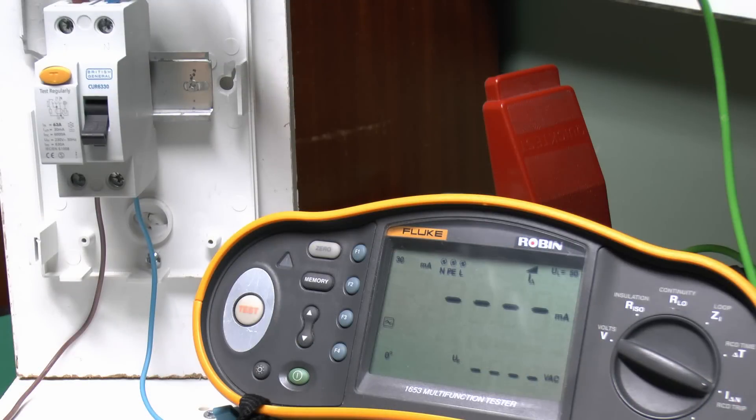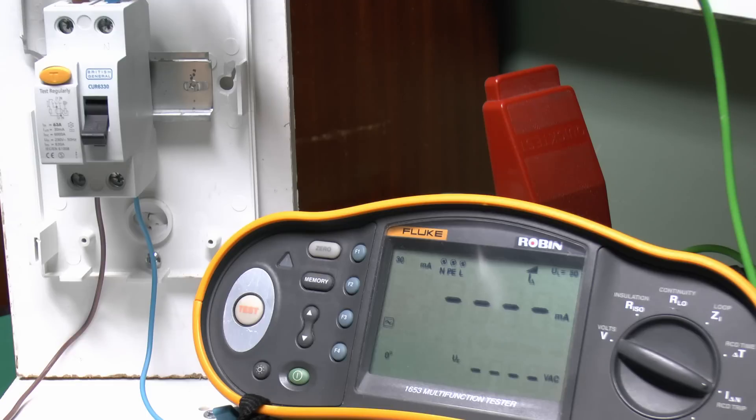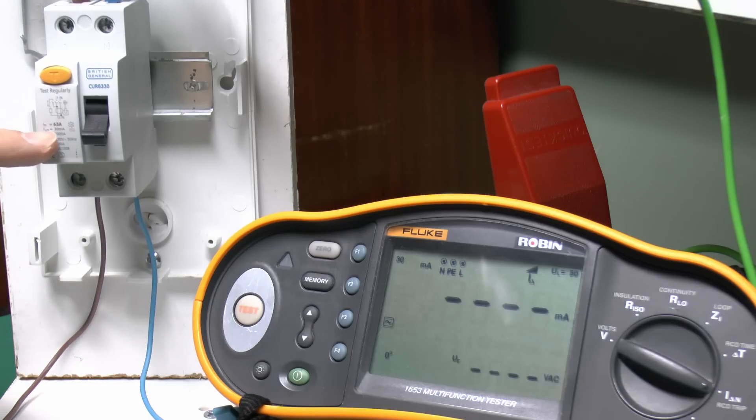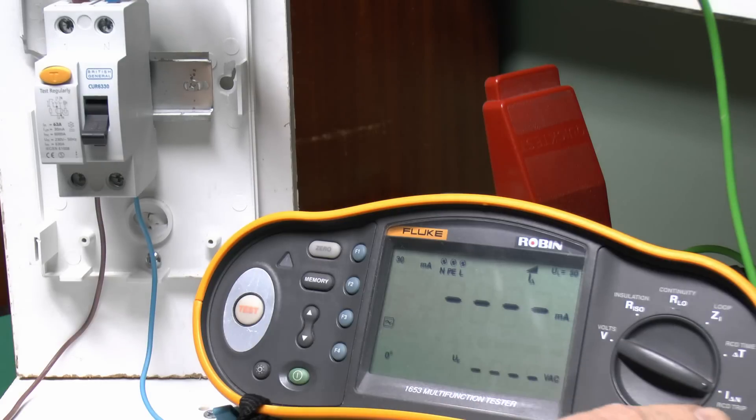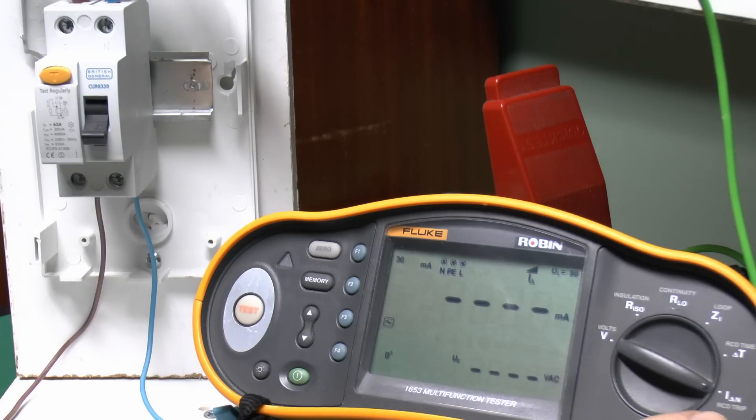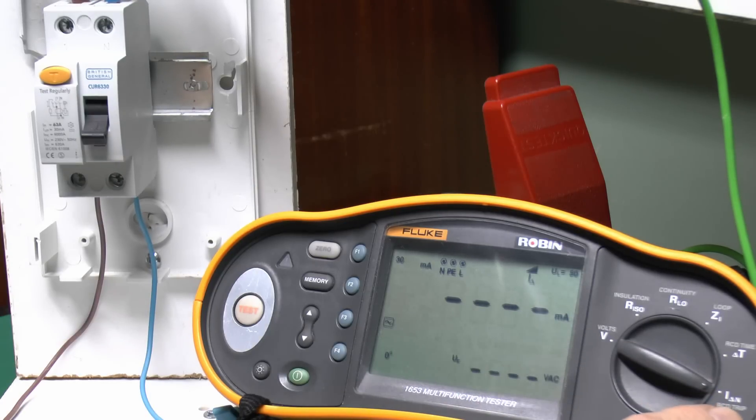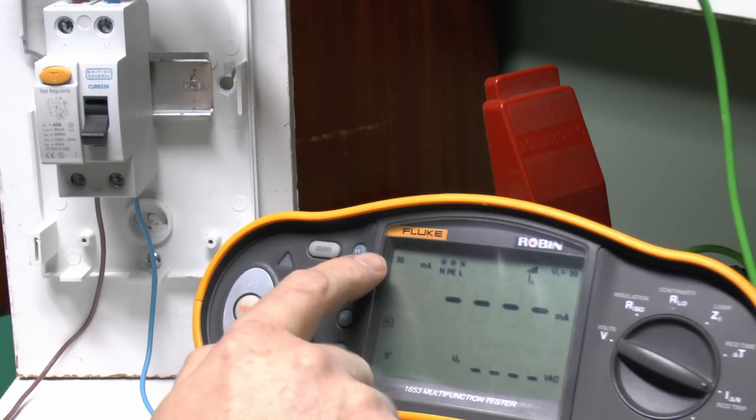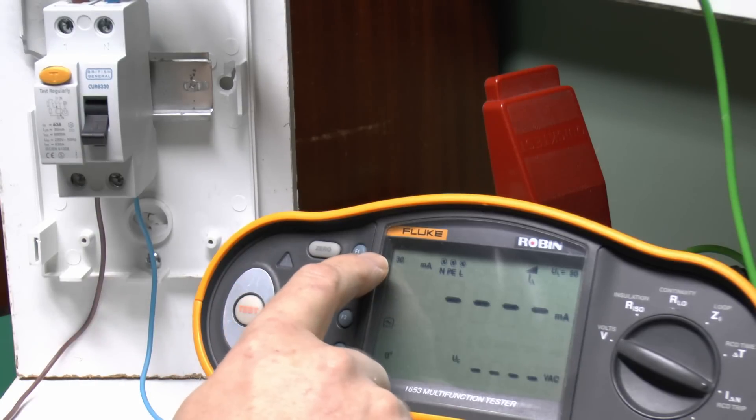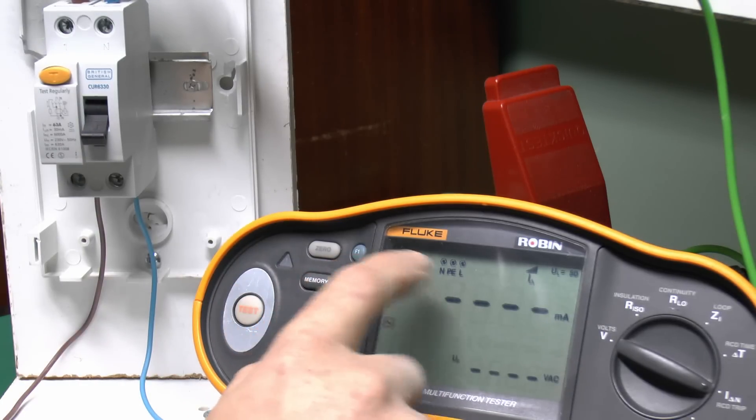Now, there's two basic types of tests which you can do on RCDs and the first one is the current it actually needs to cause the device to trip. And in the case of this particular one, it's a 30 milliamp device, so you would expect it to trip at or slightly below that tripping current. And to do this, we'll just select the appropriate setting on here, which is the I-delta-N setting. And then we just need to select here the correct rating of RCD, so in this case the 30 milliamp variety.